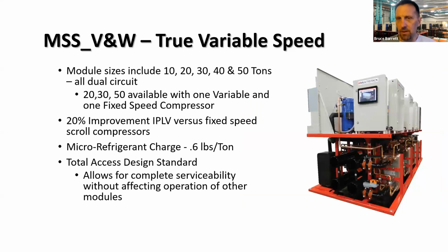Variable speed compressors. How do I know they're variable speed? They're blue. We happen to use the Danfoss line of compressors. They are limited right now to 50-ton modules. It is a great improvement in IPLV on water-cooled jobs, about 20% better than fixed. Better temperature control, less compressor cycling, low inrush. It is about a 15-20% add, but if you're looking for tighter temperature control, very energy conscious, and still very low refrigerant charge, our variable speed offering is a great opportunity for you.